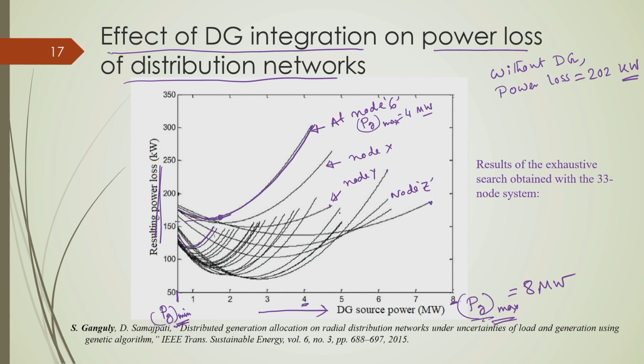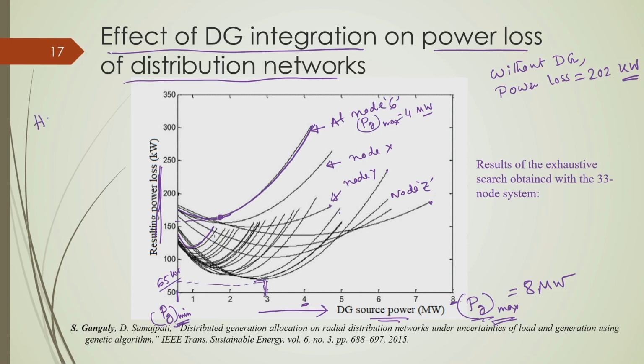There exist some locations where you get the minimum value of power loss, as low as near 65 kilowatts, corresponding to an optimum DG power value near 3 megawatts. So there are some locations where you get this minimal power loss, and out of these, one should be the best location for DG integration in order to minimize the power loss. Here our criteria is to minimize the power loss, and based on this same analysis, there is a concept called hosting capacity.